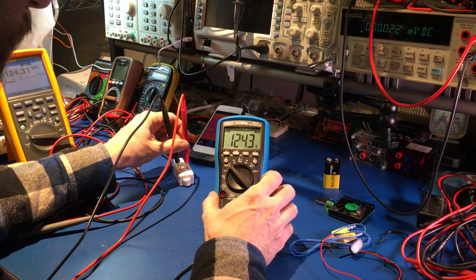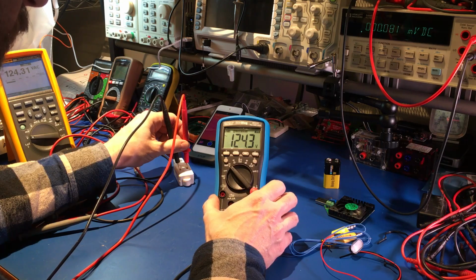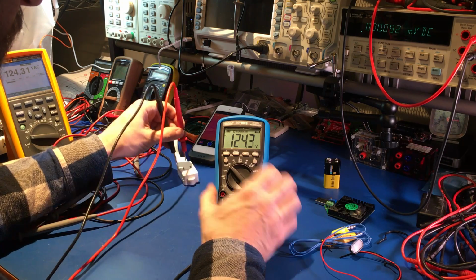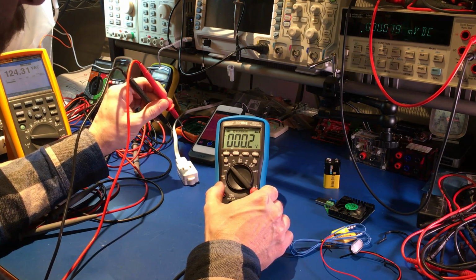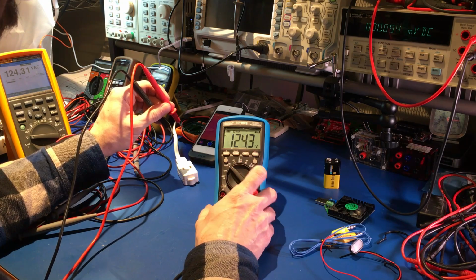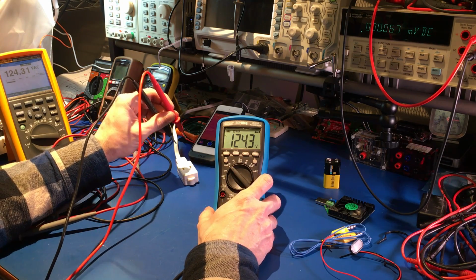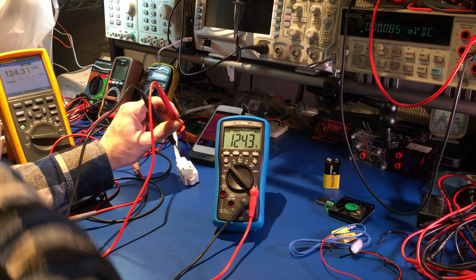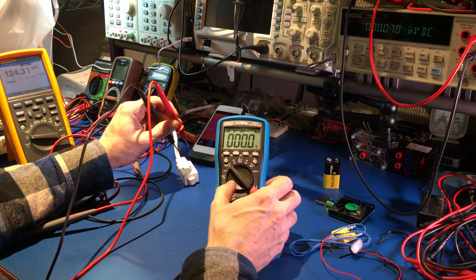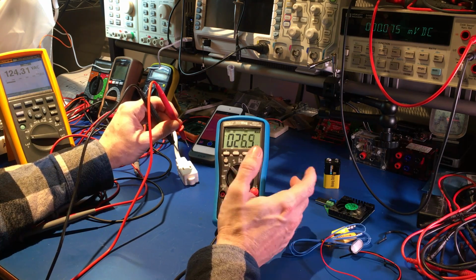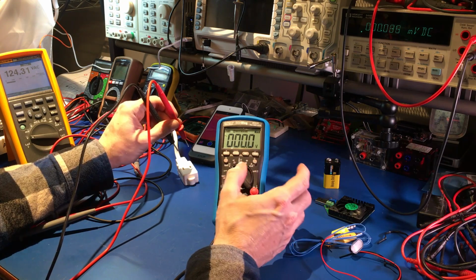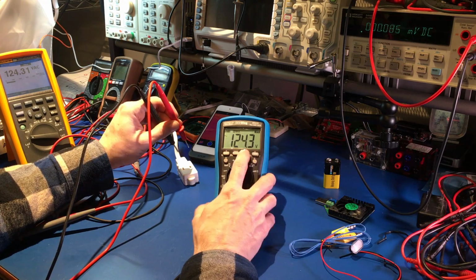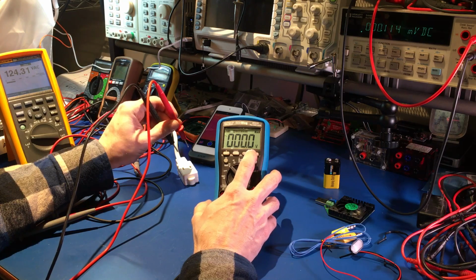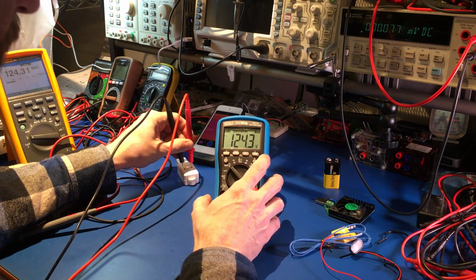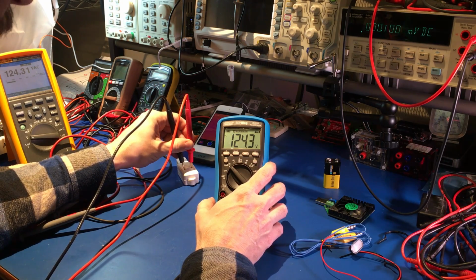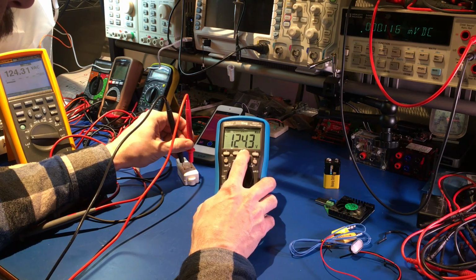Go back in here and we'll check our recorded readings for our min-max. And as it picks up and zeroes out, there it goes. So our maximum was 124.3, which matches the 124.31 on my Fluke here. The minimum 0, and the average, of course, is a constantly changing variable. But all in all, that's exactly dead on with the Fluke. Can't complain with that. That is perfect. Very good, dead on.